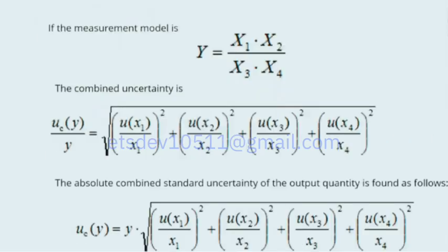And this is just to reiterate that if you're using a formula such as this, which we probably use for moisture, or in terms of concentration, then you would use that combined uncertainty. The combined uncertainty, as I showed you, is the sum of the squares of the relative standard uncertainties, which you can see. And here the combined uncertainty is divided by the measurement value, so when you are expressing this, it will go to the right-hand side. As I said, there is no rule of thumb, but you can use it for high and medium concentrations. But at low concentrations, avoid using this relative standard uncertainty.